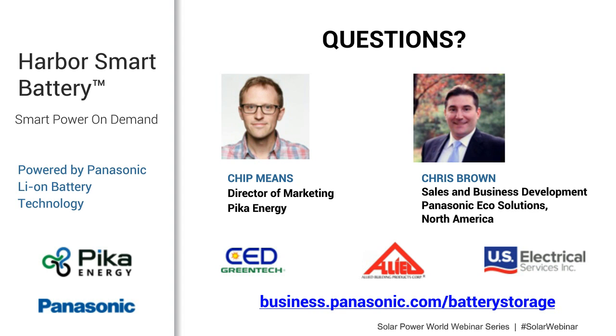Yeah, and I'll just add that for folks who are on the event here and have installed the Energy Island system, and I'm seeing a lot of familiar names on here, it's probably a little mind-blowing to hear that, because we always say don't parallel the inputs, but really, since the HIT module has a high voltage and a low current, the input ampacity of a PV Link is 13 amps, and so 2 parallel substrings of the HIT module is actually fine with PV Link, and as Chris says, it's really a nice design because you can get 8 of them and take advantage of that really awesome solar module with the Energy Island system.